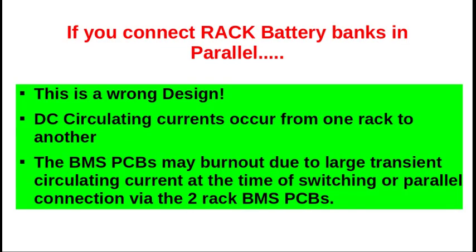What will happen if you connect two rack battery banks in parallel? Actually, this is a wrong design. The DC circulating currents of the order of thousands of amperes will occur from one rack to another. The BMS PCBs may burn out due to the large transient circulating current at the time of switching or parallel connection via the two rack BMS PCBs.